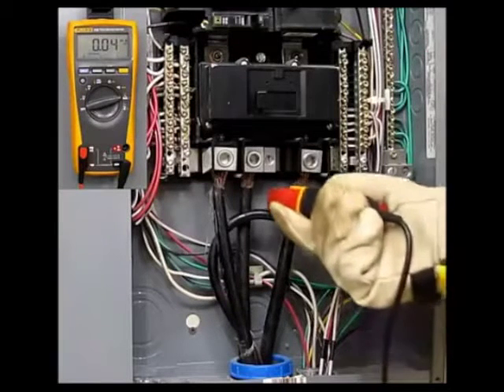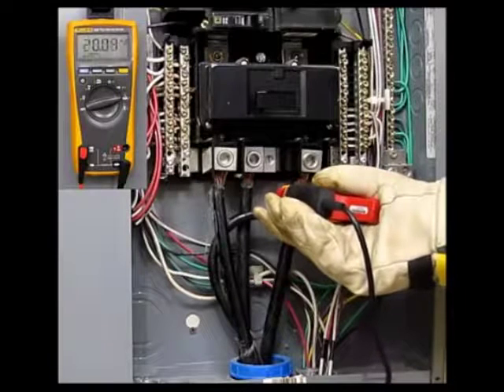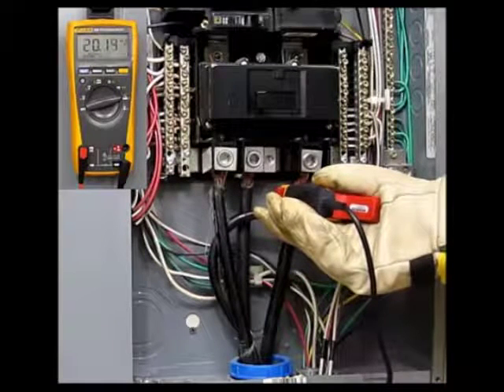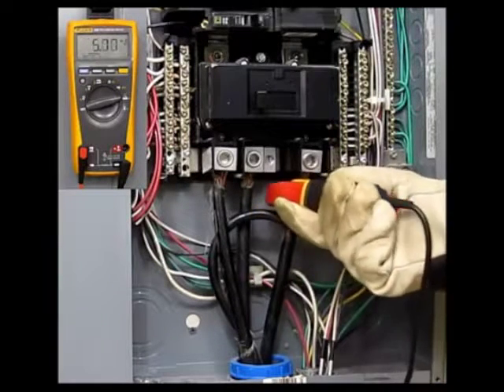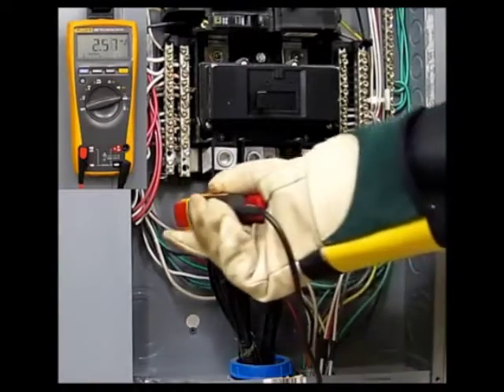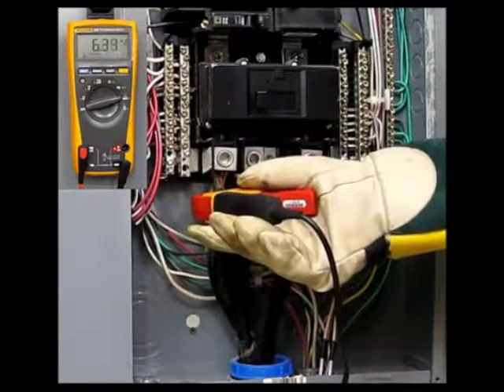In this video, we are performing a clamp-style current test on a single-phase panel. We will be testing the hot conductors to measure the imbalance between them. Notice that one leg is substantially higher than the other.